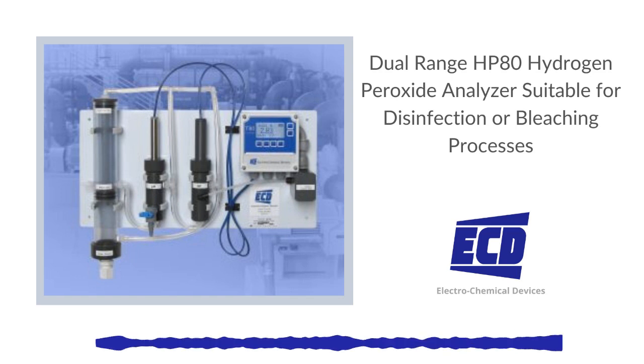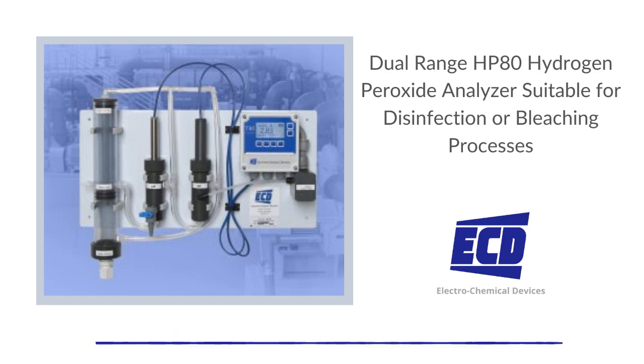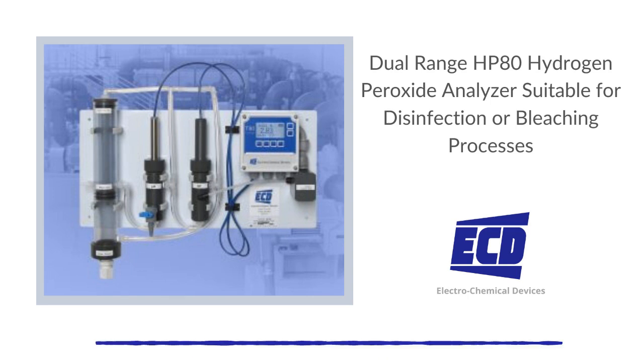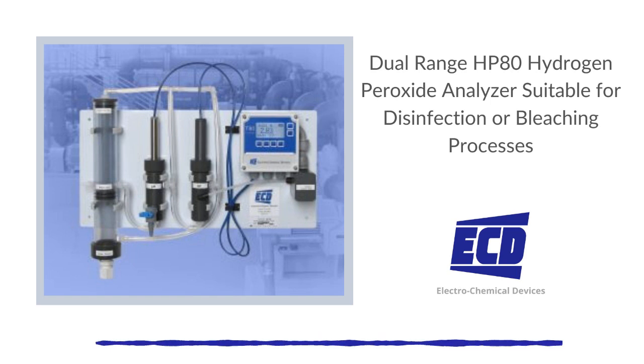The HP80 Analyzer features amperometric H2O2 sensors. These amperometric sensors are manufactured with a gold cathode, a silver anode and a rugged microporous membrane. The H2O2 sensors are smart sensors with their identity and calibration information stored internally. Communication between the T80 transmitter and the H2O2 sensor is via Modbus. The sensors are flow sensitive, requiring a minimum flow rate of half a foot per second. Above this flow rate, the reading is virtually independent of the flow rate.